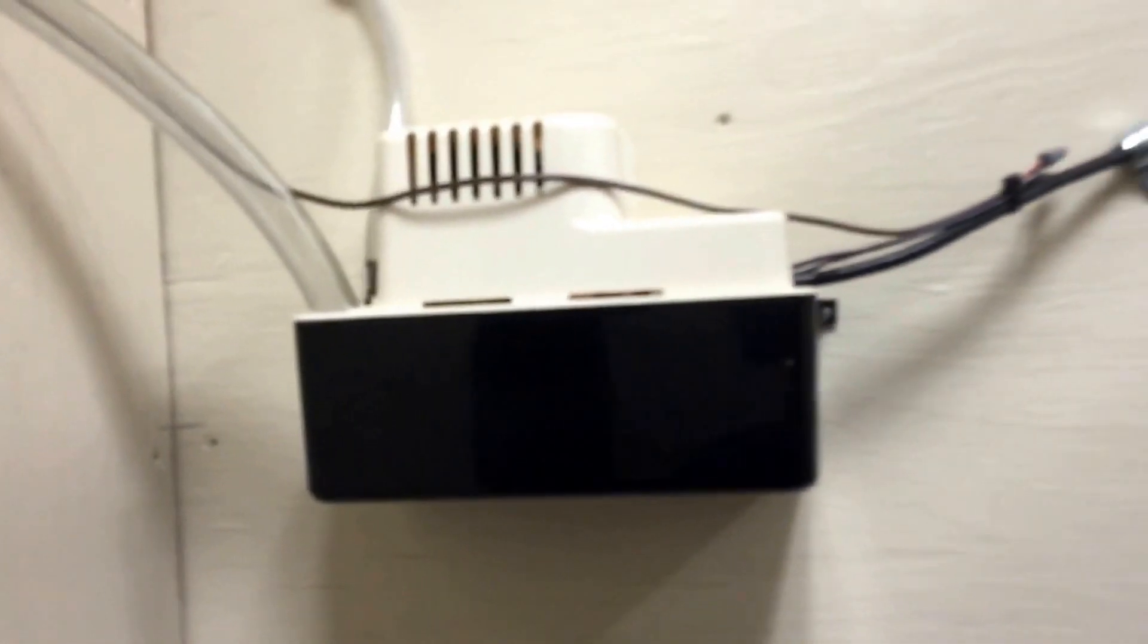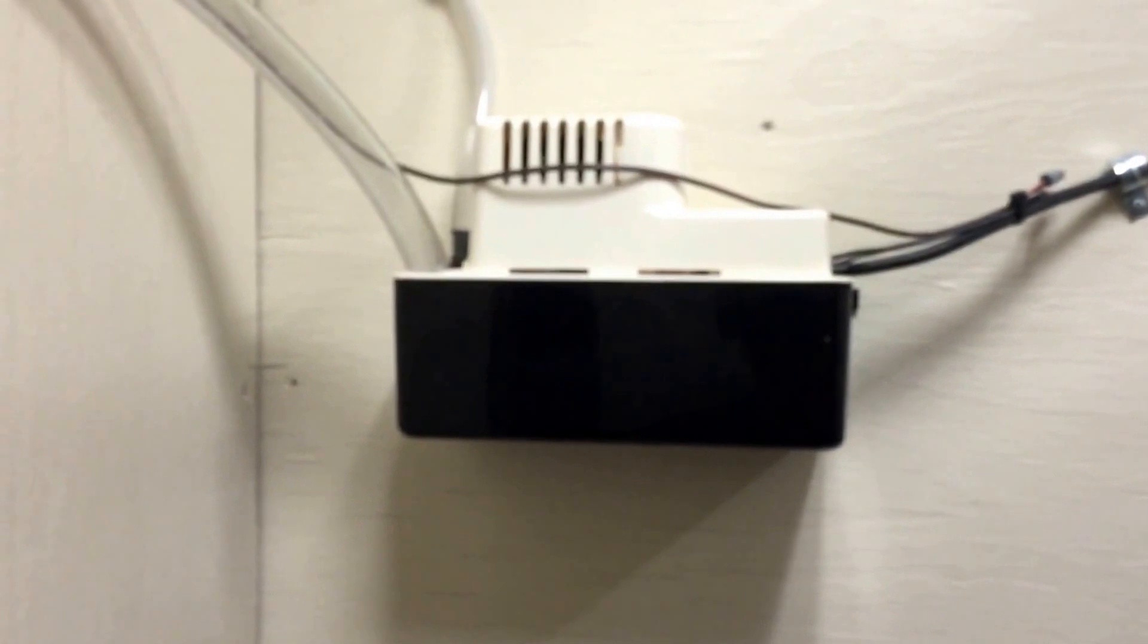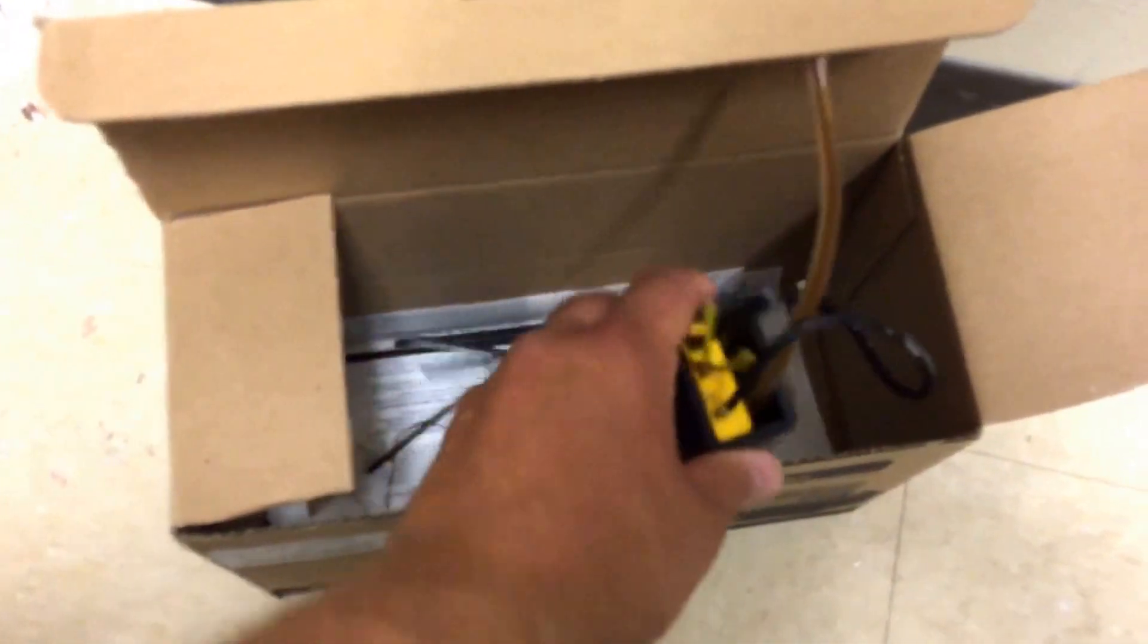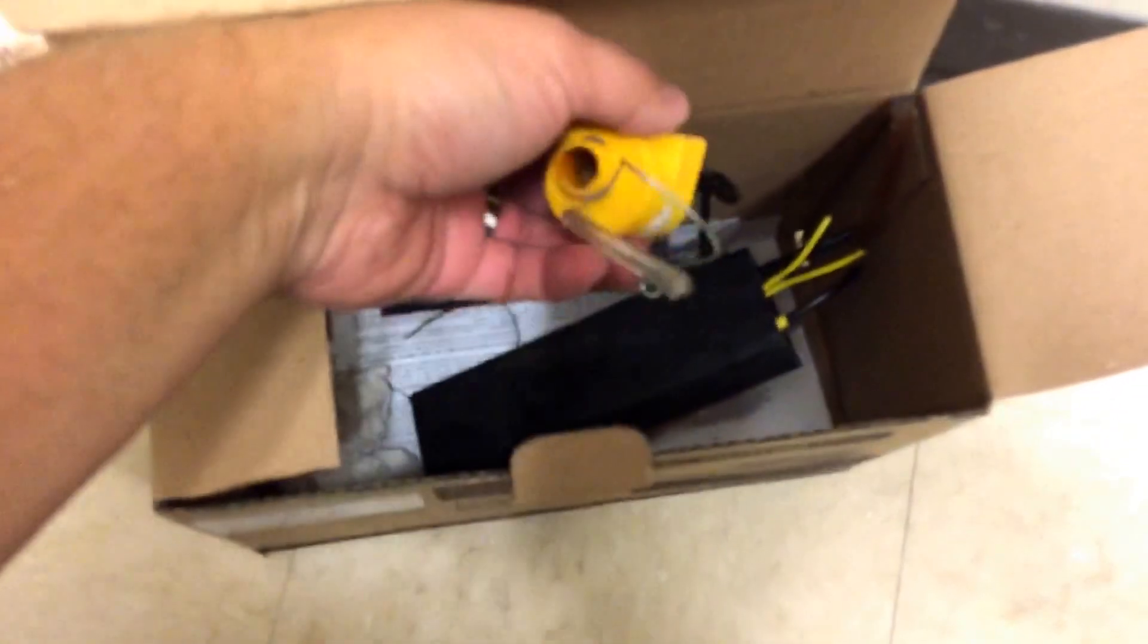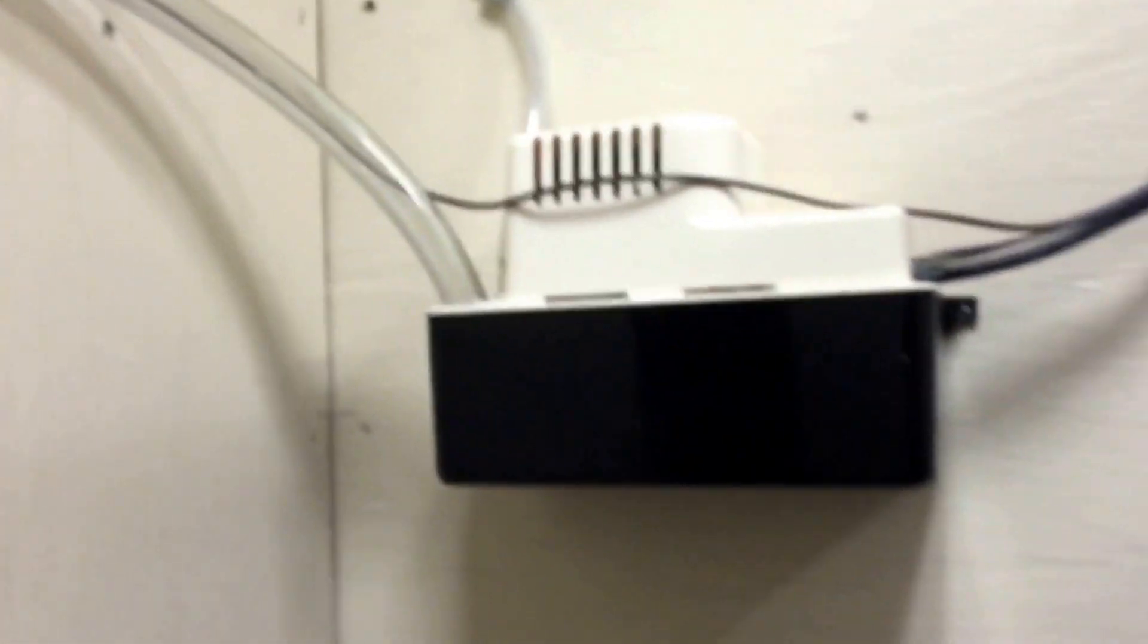Okay guys, here's what I wound up doing. On that condensate pump, this little mini split condensate pump here. This thing was like a special order from EMI. It's going to cost over $400. And nobody had one in stock at all anywhere. So here's my solution. Mount a little giant condensate pump up on the wall.